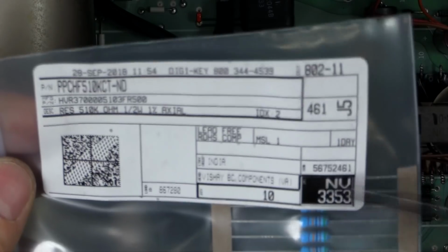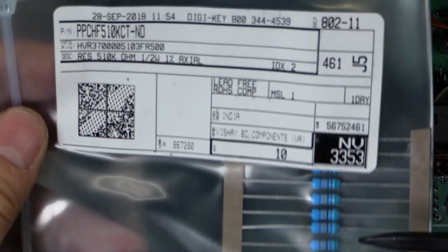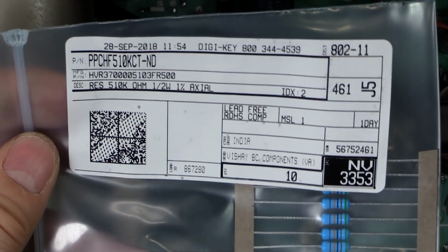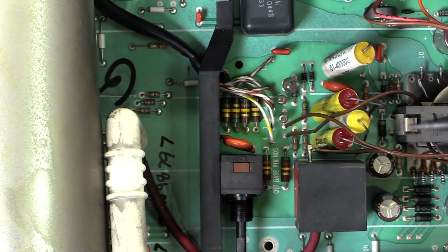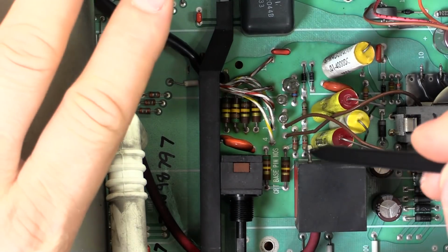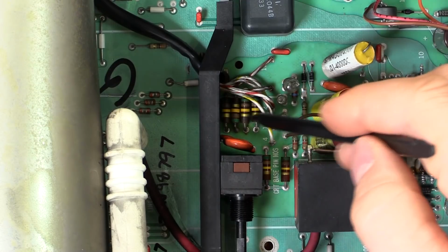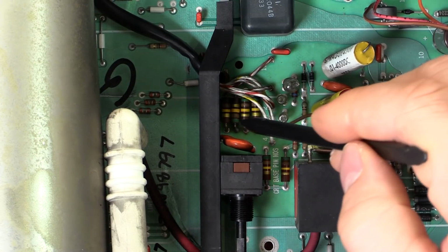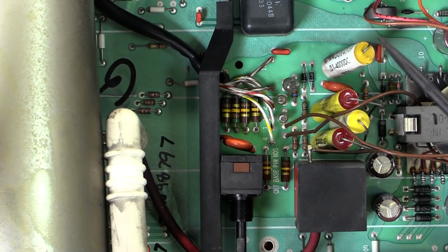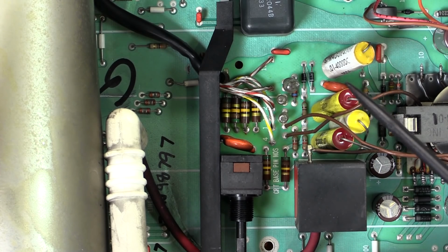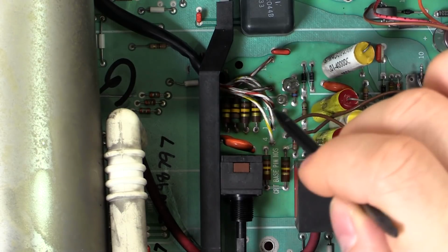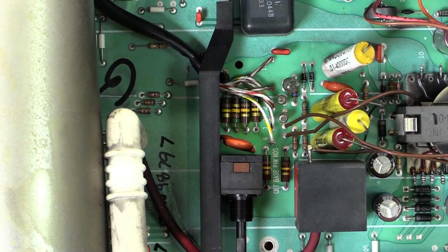So I'm going to replace them with metal film, which are a lot more reliable than the old carbon composite, and that will stop this from becoming faulty. At the moment mine isn't, but it is a common fault where these will go open or close circuit and mess up your focus. So if you have one of these and the focus doesn't work right, it's always out of focus and you can't dial it in, check this area of the circuit and replace those resistors. So we're going to do that.